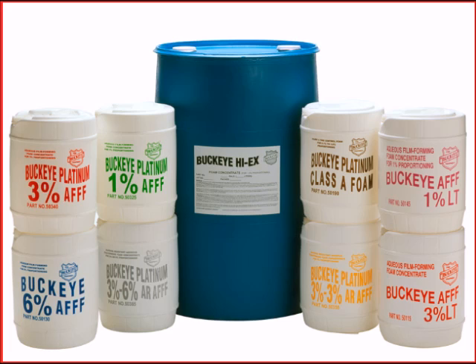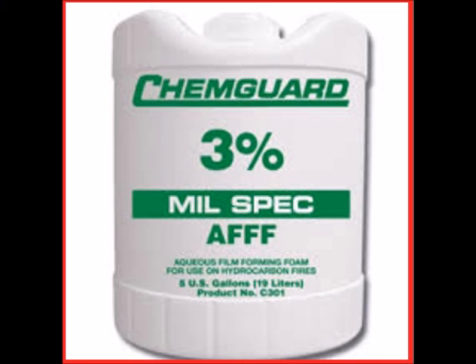In the 1960s, National Foam, Inc. developed fluoroprotein foam. Its active agent is a fluorinated surfactant that provides an oil-rejecting property to prevent contamination. In general, it is better than protein foam because its longer blanket life provides better safety when entry is required for rescue. Fluoroprotein foam has fast knockdown characteristics and can also be used together with dry chemicals that would otherwise destroy protein foam.